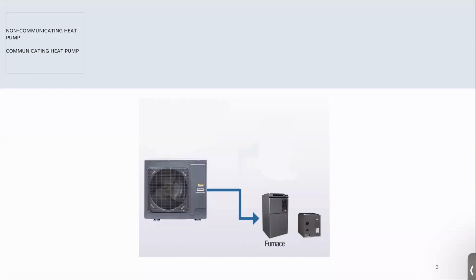We have a non-communicating heat pump and a communicating heat pump. With the communicating heat pump, we'll go through sort of the first two would be a thermostat type. Non-communicating, we have a basic North American thermostat. That would be a 24-volt signal. Switching on-off signals is something that we all know very well. All service techs understand them, and it's been in the industry for as long as I can remember.